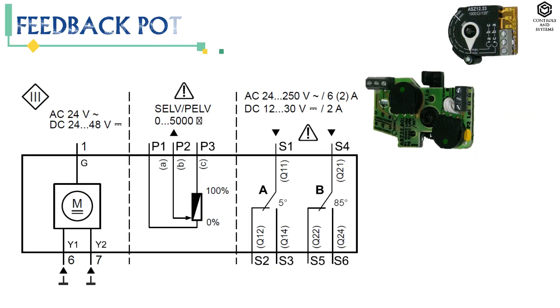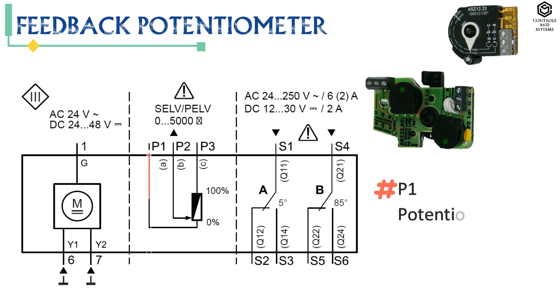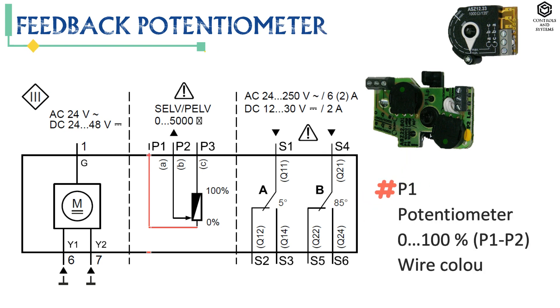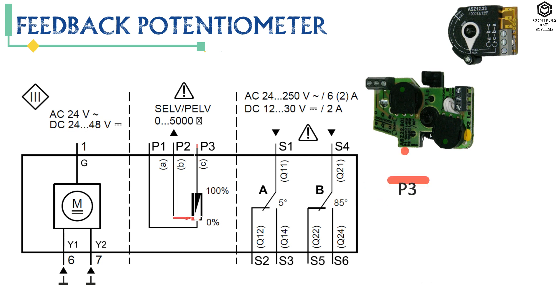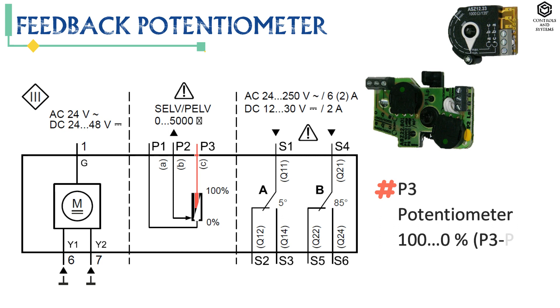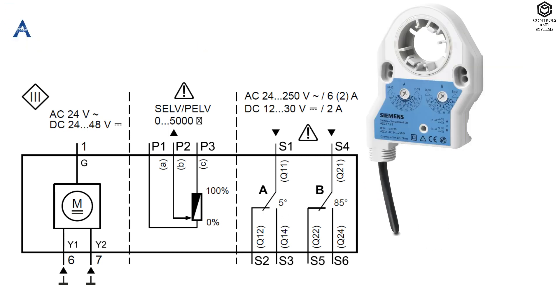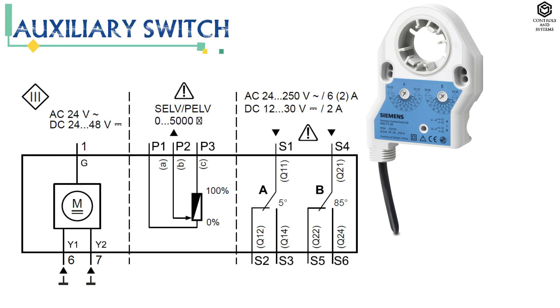Feedback potentiometer: terminal P1 is potentiometer 0 to 100 percent, wire color white and red. Terminal P2 is potentiometer pickoff, wire color white and blue. Terminal P3 is potentiometer 100 to 0 percent, wire color white and pink.